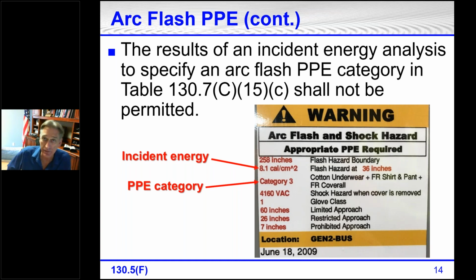This one is showing category 3. We're allowed to put one or the other on there, but not both. It wasn't specifically stated several editions back, and I know a lot of companies did that, but let's look at the potential problem if it is done. In this case, it does show 8.1 calories per square centimeter at 36 inches.